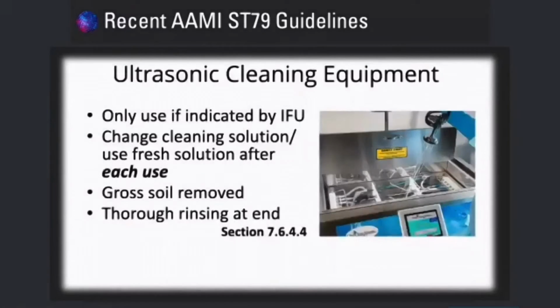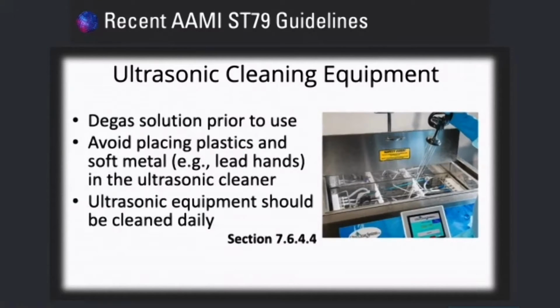On the topic of ultrasonic cleaning, make sure to only clean those instruments indicated by the IFU. Use fresh cleaning solution after each use. This is particularly important for ophthalmic instruments because you don't want detergent and other constituents remaining in the basin and staying on an instrument and getting reused. TASS is not a pretty thing, and I know you know that. We also suggest that you even have your own dedicated machine for ophthalmic purposes. Gross soil should be removed, with thorough rinsing at the end. Again, TASS can occur because you haven't rinsed the instruments thoroughly, because of any residual detergent that may have been left. So, thorough rinsing at the end. Just keep these things aware and ever present in your mind.